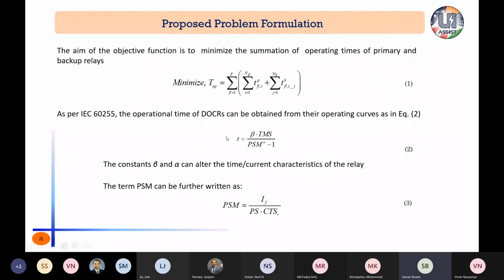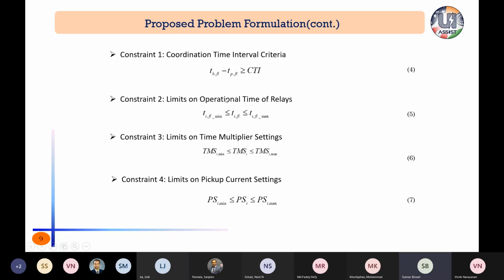So here we propose, instead of taking fixed values of beta and alpha, to consider variable beta and alpha in the relay characteristics modeling. And this PSM can be written as the fault current divided by plug setting times CT ratio. The objective function stated in the earlier slide needs to be minimized subject to these constraints. The first constraint is the coordination time interval criteria, which says that for any fault at a certain location, if the primary relay fails to operate, then the backup relay should operate after a certain time interval, which we call CTI or coordination time interval.